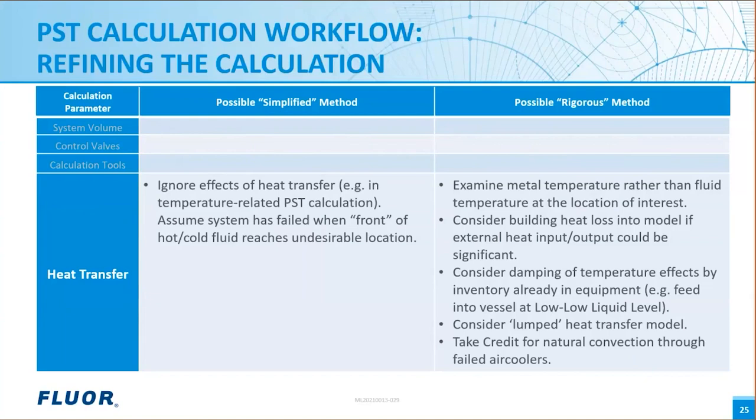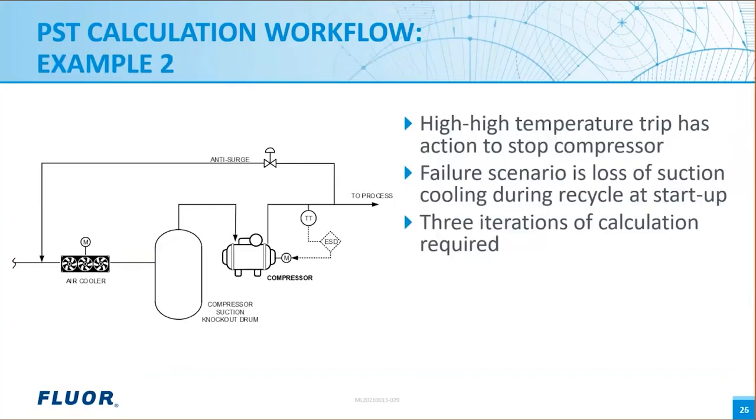The scenario considered here was a sour gas compressor, and the particular scenario concerned was startup. During startup of this compressor, it would be operated using fuel gas on recycle. The fuel gas would go around through the air cooler. The concern was that the air cooler might fail during startup, and that would lead to warm gas going to the compressor suction, which would then lead to very hot gas at the compressor discharge and potentially exceeding the piping design temperature, which might lead to loss of containment or overstress and so on.